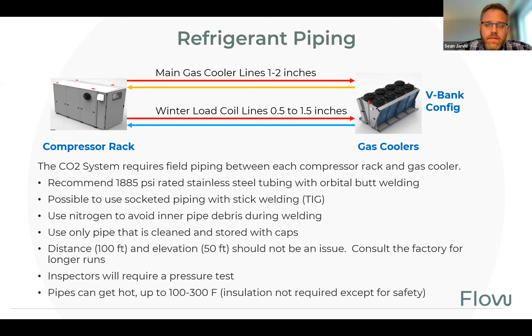Now I want to highlight installation and maintenance a little bit. So on an initial startup, it is really important that we pull a good vacuum. All the great things you would do for any refrigerant system, you really should do here. It's still a refrigerant. We want to make sure we use refrigerant grade CO2, none of this beverage grade CO2, because it has little droplets of moisture in it that becomes a problem.